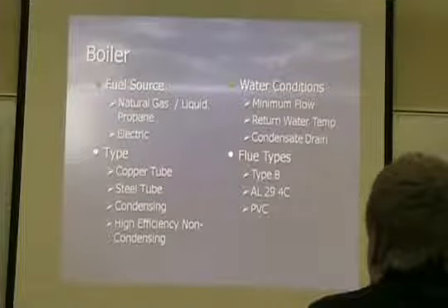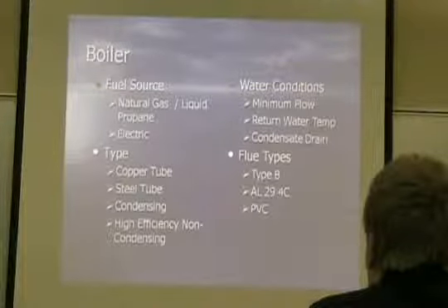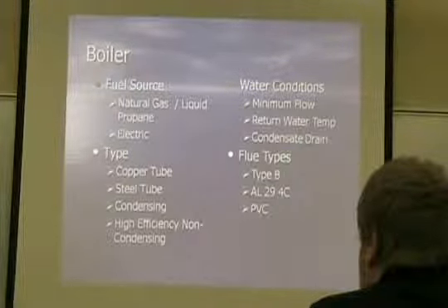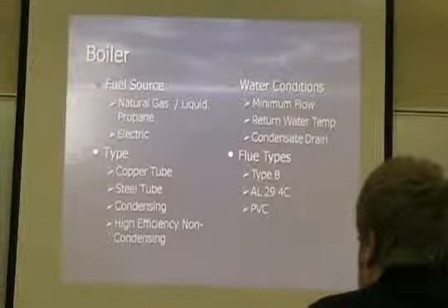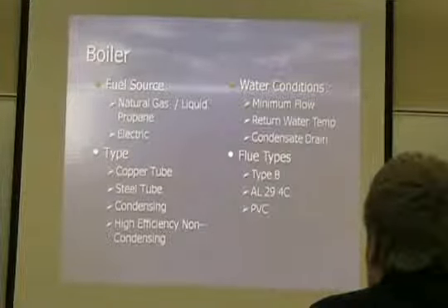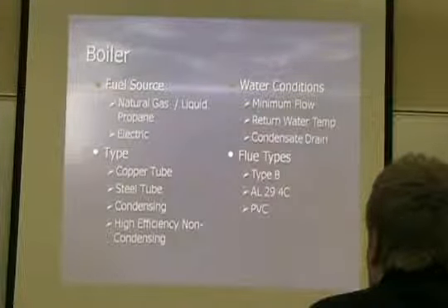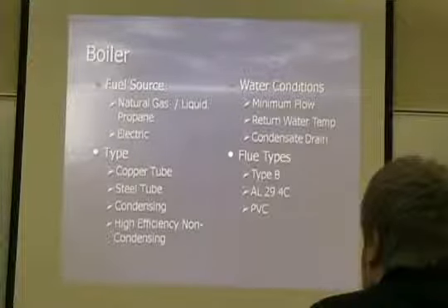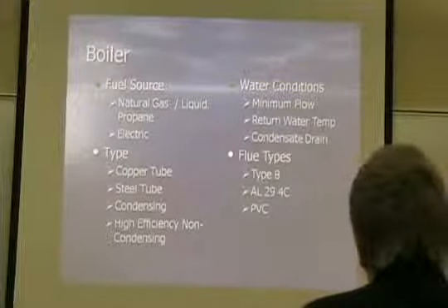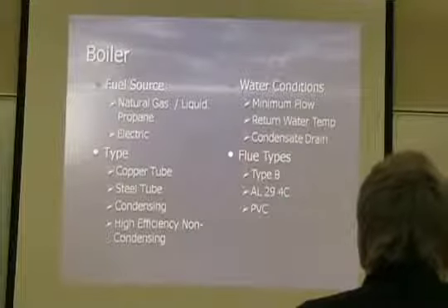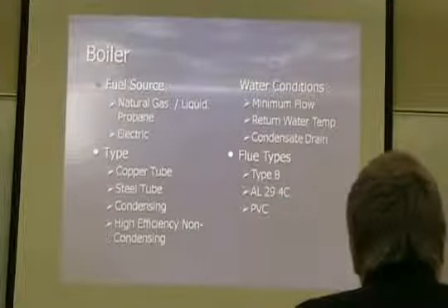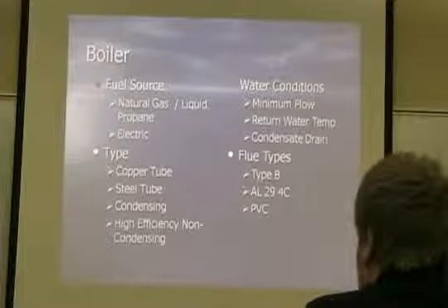In a condensing boiler, you've got the condensate drain coming off the boiler that's kind of acidic. Sometimes you have to run your condensate drain off your condensing boilers through a neutralizer. Flues: standard boilers, we talked about that the other day, type B. The condensing boilers, some of them use AL 29-4C stainless. Some of them actually use PVC because your condensing temperatures are so low and your efficiency is so high that your boiler temperature is generally less than 110 degrees coming off the boiler, whereas in a standard water tube boiler it might be 350 degrees.